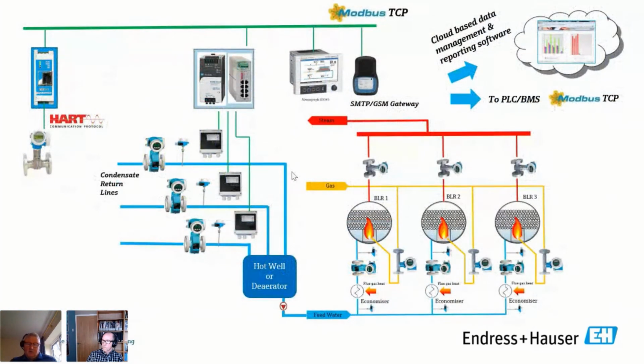We talked about digital data before. Obviously we've got to collect the data, and the best, most efficient and most accurate way of doing it is to look at digital protocols, not the pulses or analog signals from these meters, but purely the digital information. Almost all of those flow meters I showed you, in fact all of them, have a digital protocol as standard anyway. It's called HART. It's been around for decades, and some sites will only take HART, they won't take anything else.